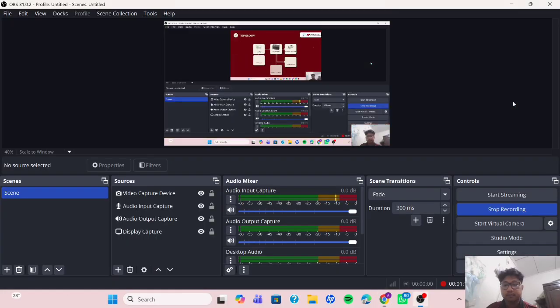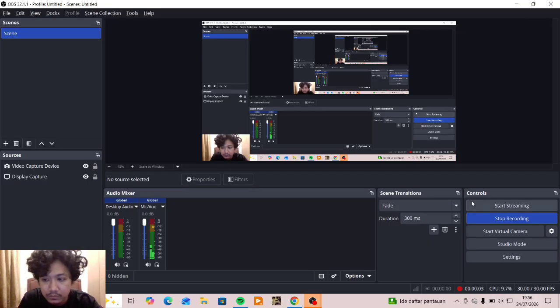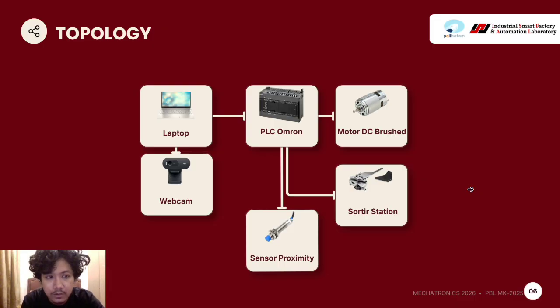Okay, my name is Dio Andrian. This is the topology of our project. First, starting from the left, we have the laptop and webcam. The laptop is used to program, monitor, and control the Omron PLC. Meanwhile, the webcam is used to capture images to monitor the sorting process in real time. Second, the center of the system is the Omron PLC. The Omron PLC acts as the main controller. It receives input signals from the proximity sensor, processes the data according to the program logic, and controls all output devices. Third, the PLC receives feedback from the proximity sensor.